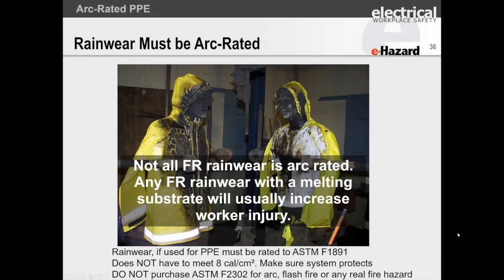Rainwear can melt. If they claim it's FR, it might use 2302, it might use a small-scale test method. If it's not 1891 with an arc rating, don't purchase it. Do not purchase ASTM F2302 as a standalone standard for flame resistance in any material.